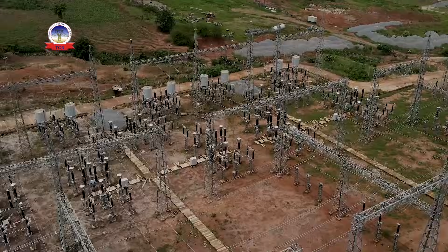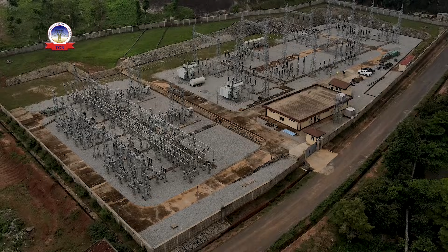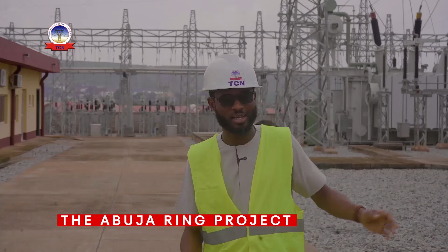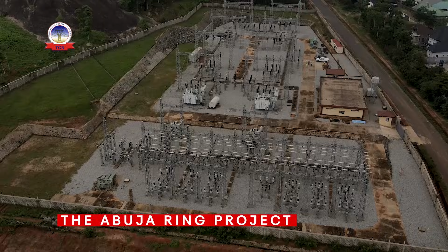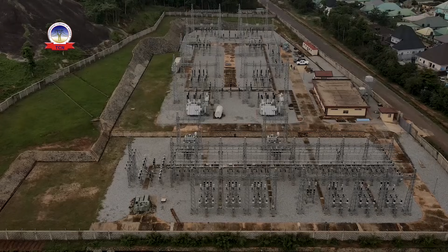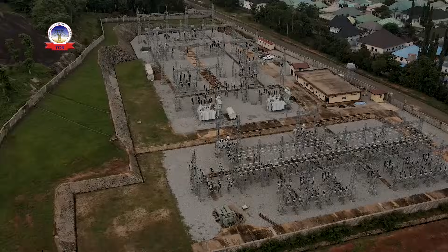This is strategic planning for tomorrow. As the full ring nears completion, the impact on grid stability, efficiency, and energy access will be evident throughout the capital. We are currently at the 2x60 MVA 132kV transmission substation here at Wumba, Abuja. As you can see behind me, it has two transformers of 60 MVA each, giving out up to 96 megawatts of power to the national grid.